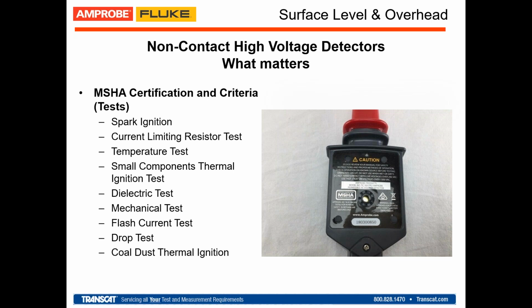Our TIC 300, the product that we're presenting right now in the next slide, is a non-contact voltage detector that has been MSHA certified as intrinsically safe equipment. MSHA is basically the counterpart of OSHA, but for the mining industry. And what does that mean? What is MSHA intrinsically safe certified equipment? It is equipment that has gone through a set of 9 or 10, I believe, different tests: spark ignition, current limiting resistor test, temperature, small components ignition testing, dielectric.